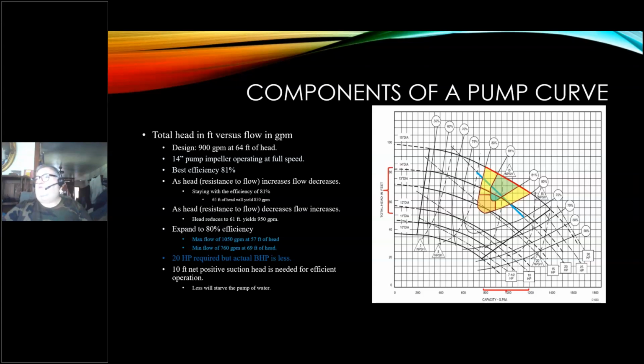65 feet of head will give you 850 GPM. So I'll pick the extreme, okay? That's the highest flow I can expect. My best efficiency falls right in here in that deep green zone. But then my flow goes down around 900. So that's really where I want to be.